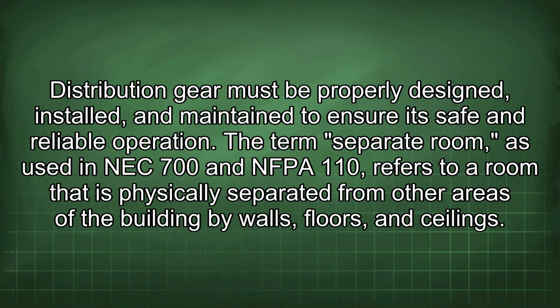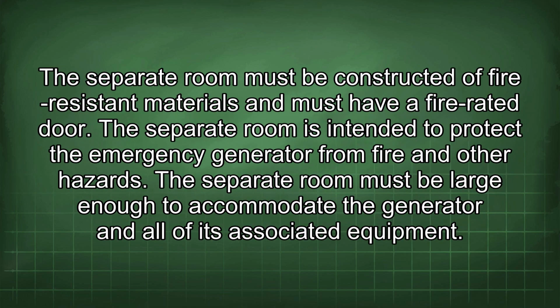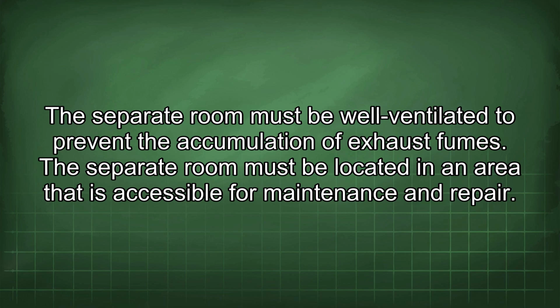The term separate room, as used in NEC 700 and NFPA 110, refers to a room that is physically separated from other areas of the building by walls, floors, and ceilings. The separate room must be constructed of fire-resistant materials and must have a fire-rated door. The separate room is intended to protect the emergency generator from fire and other hazards. The separate room must be large enough to accommodate the generator and all of its associated equipment. The separate room must be well ventilated to prevent the accumulation of exhaust fumes. The separate room must be located in an area that is accessible for maintenance and repair.